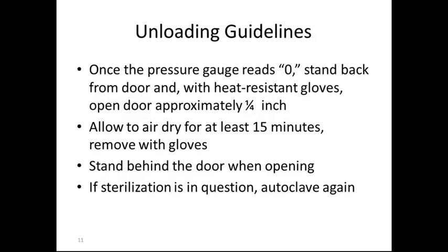Unloading guidelines. Once the pressure gauge reads 0, stand back from the door and, with heat-resistant gloves, open the door approximately a quarter inch. Allow the air to dry at least 15 minutes. Remove the materials in the autoclave with gloves.